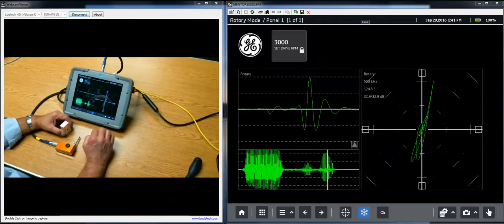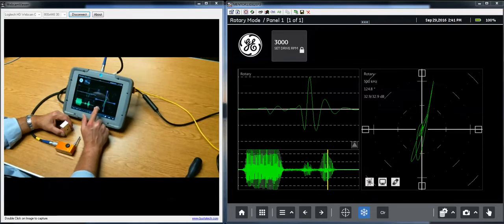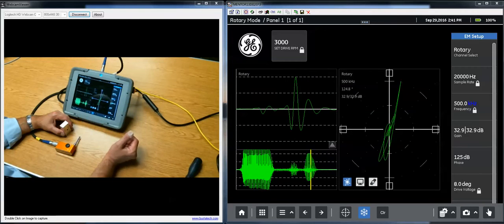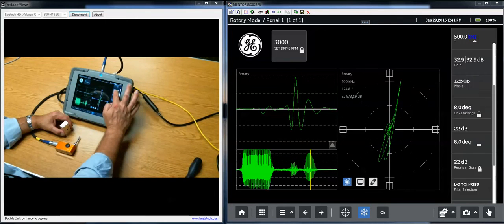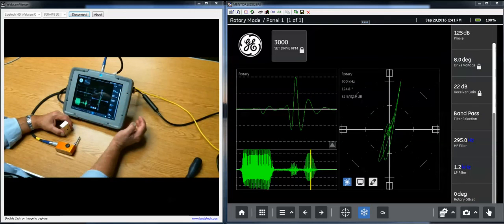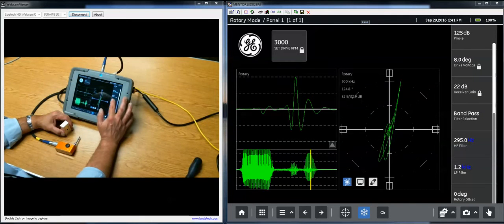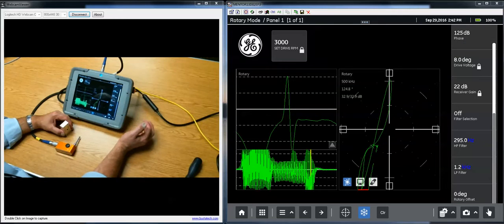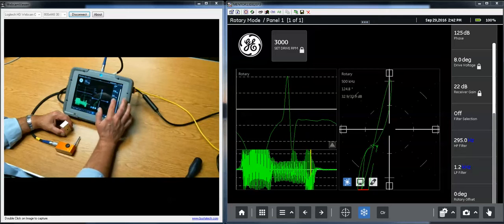Normal surface inspection, you might run 1,000 hertz sample rate. You're taking 1,000 samples per second. Here we run 20,000 samples per second. Again, because the probe itself, the probe element, the coil is so tiny and it's rotating at such high speed, we use a much higher sample rate. Another feature of rotary inspection is that we tend to use filtering quite heavily. If we turn the filtering off, that's the kind of indication that you're getting from your signal. So it can be a little bit difficult to interpret.